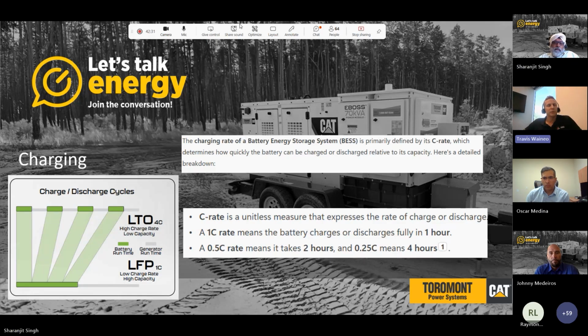Yeah, definitely. So when we talk about battery C rate, essentially the easiest thing to do is look at an application. So if you have a 100 kilowatt hour battery pack and you charge it at 100 kilowatts, that basically means that you will charge that battery to full in 1 hour. So we call that a 1C charge rate. If you were to charge that 100 kilowatt hour battery pack at 400 kilowatts, that would be a 4C charge rate. So this battery system here, the 70 kVA, has a 25 kilowatt hour battery on it. So essentially, if you're charging that at about 28 kW, which is what that XQ35 does, it's about 45 minutes to a little bit over 45 minutes to charge that battery pack to full.